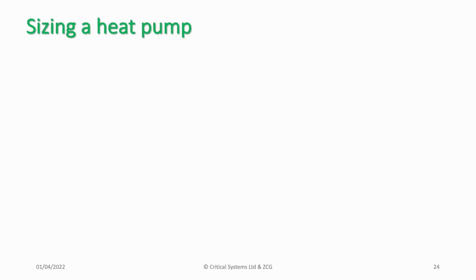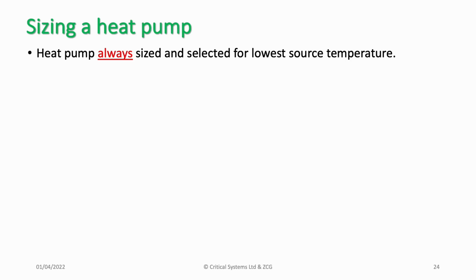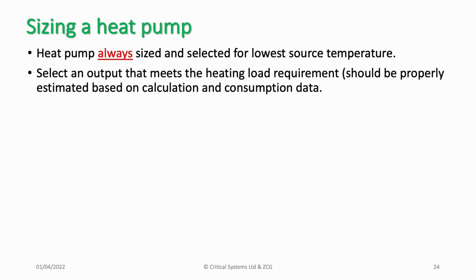So let's have a little think about sizing the heat pump. A heat pump always needs to be sized for the lowest source temperature, that winter design day condition. You need to select an output of your heat pump that meets the heating load requirement, considering both that peak load for warm-up and the steady state. Whilst you can get some information from your existing gas consumption, the load really needs to be estimated properly from a consideration of both heat losses from individual rooms within the building and a cross-check against existing consumption data.